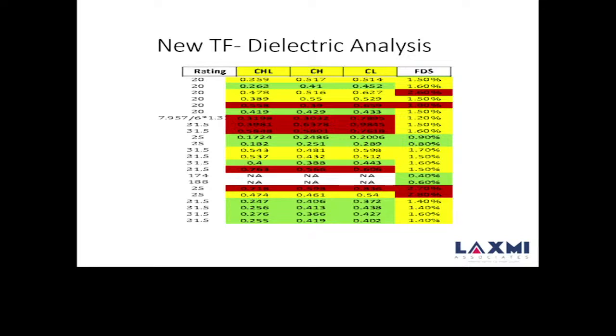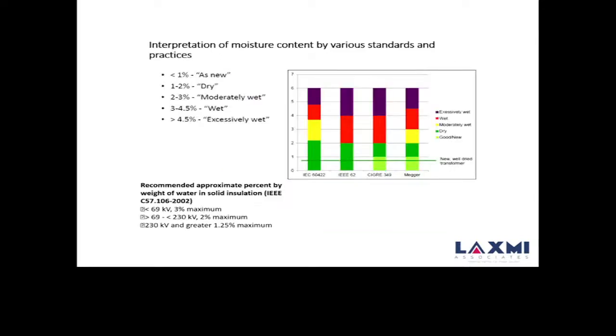Now this is a case which gave a failure in a short span after commissioning, after 2-3 years. What you see is a tan delta value here, and a moisture value of 2.6 or 1.8%, and the tan delta is also on the higher side. Normally for a good, new transformer, the tan delta benchmark is 0.5% maximum. But here the tan delta value is on the higher side, and the FDS benchmark is good for 1%. But here those values are very high.